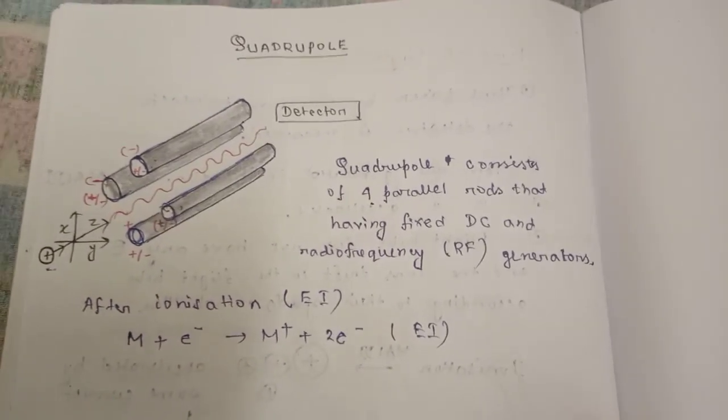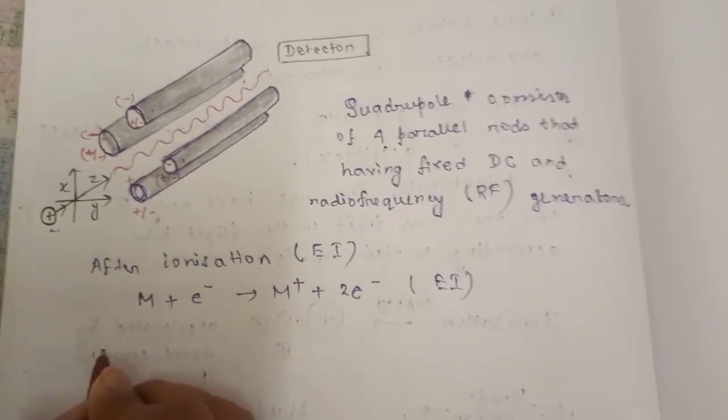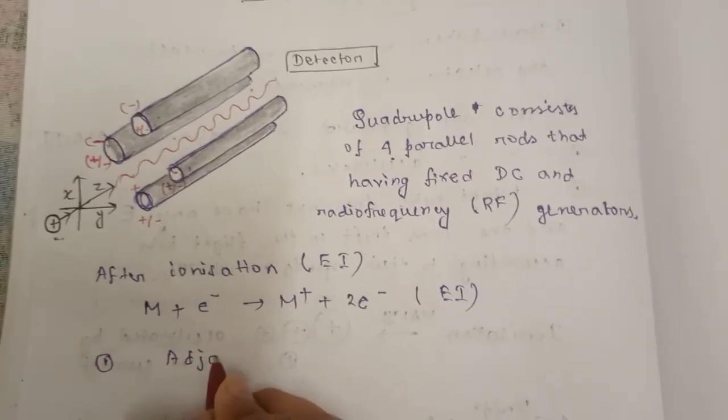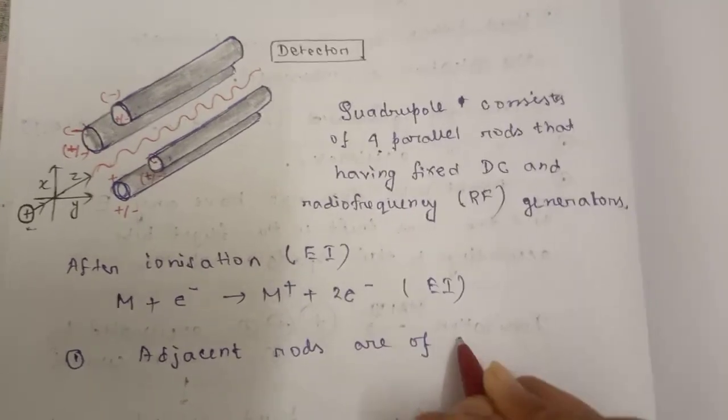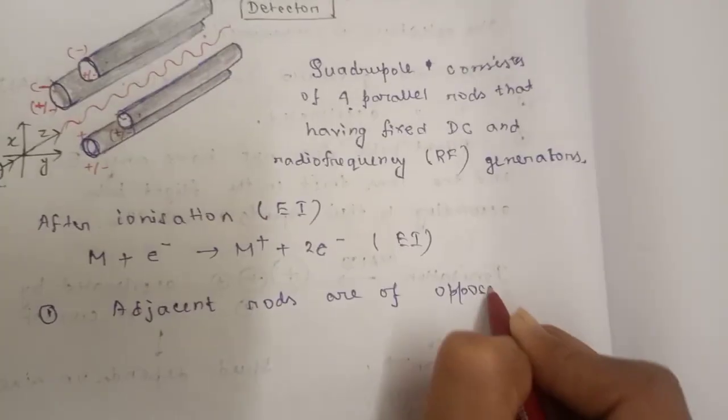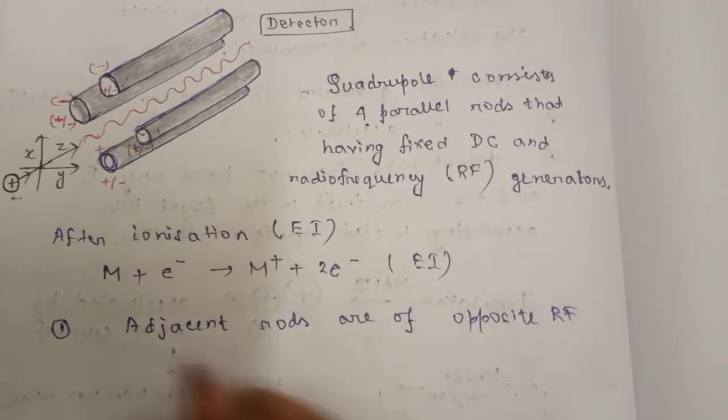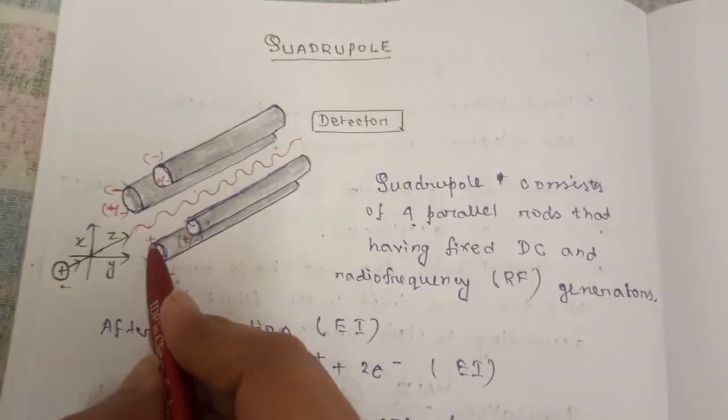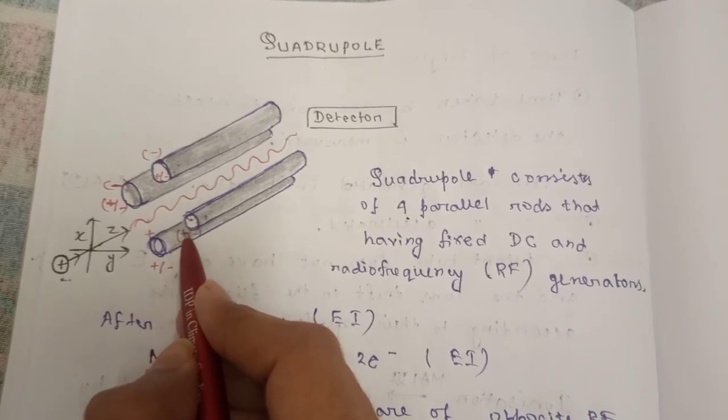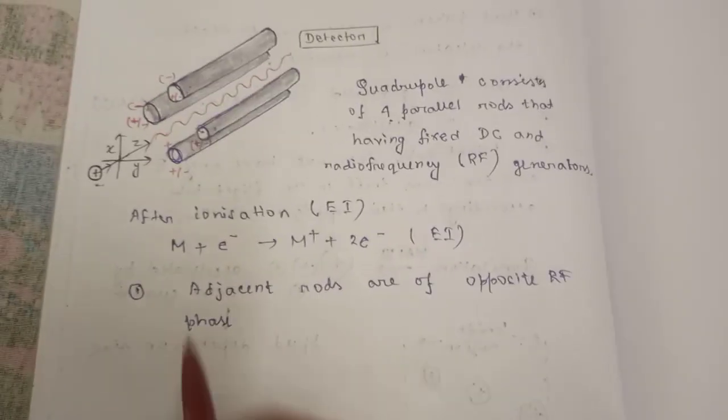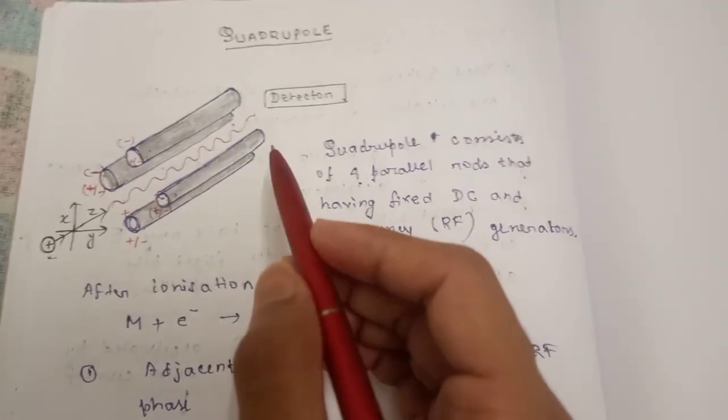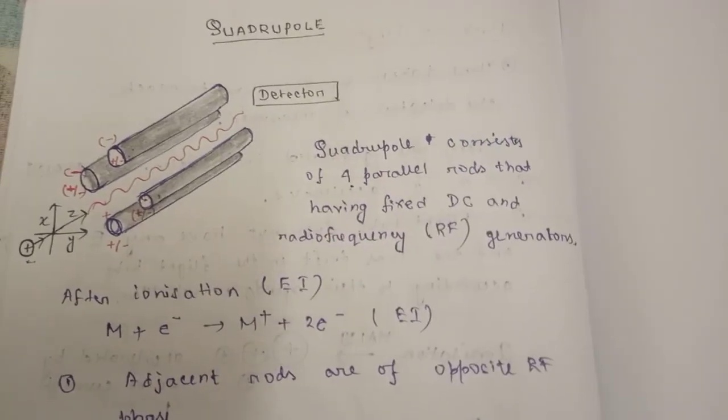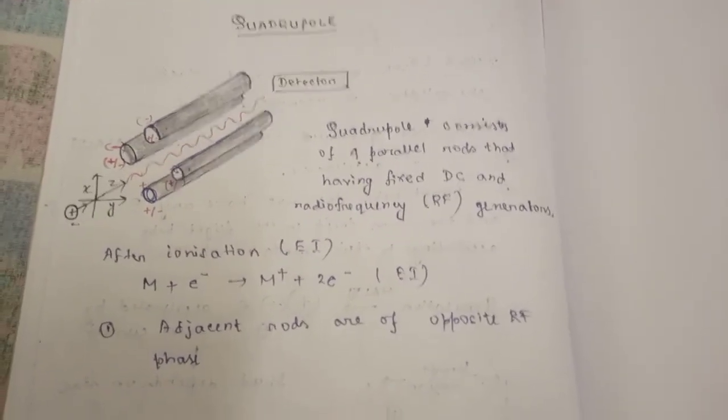One thing has to be remembered for quadrupole: adjacent rods are of opposite radio frequency phase. Here you can see plus and minus, and plus minus. They are in opposite phase, and ions will be passed through the rods and go to the detector for further analysis and electrical output. This is how quadrupole works.